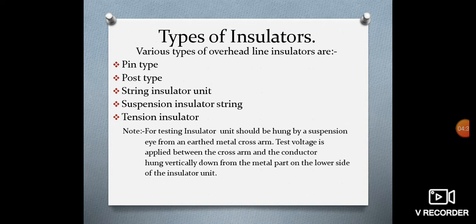Types of insulators. Various types of overhead line insulators are pin type, post type, string insulator unit, suspension insulator string and tension insulator. In the testing of insulators, we have to note that the insulator is hung by a suspension eye from an earthed metal cross arm. Test voltage is applied between the cross arm and the conductor hung vertically from the metal part on the lower side of the insulator unit. Generally, the high voltage is applied at the lower side of the insulator unit, which is hung in the upside down condition.